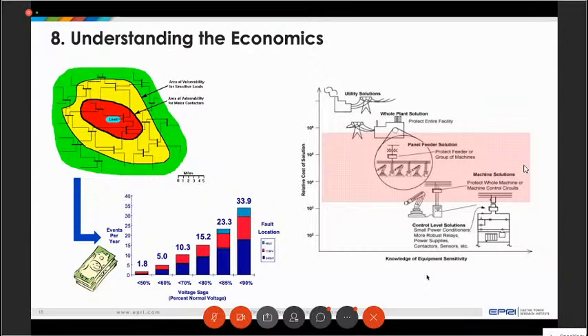If the number of voltage sags per year was 40, maybe the utility should be spending money to reduce the number of faults. One traditional power quality compatibility case is a plastics plant. Plastics plants are sensitive to voltage sags, and a sag below 70% may cause many extruders to trip offline, making a mess with plastic everywhere, requiring restart of all those extruders.